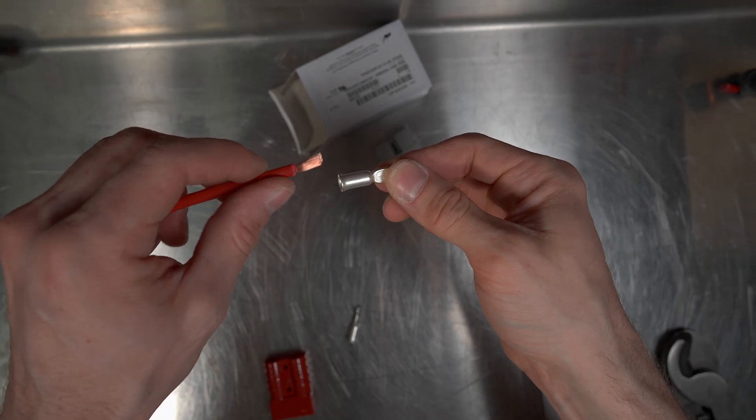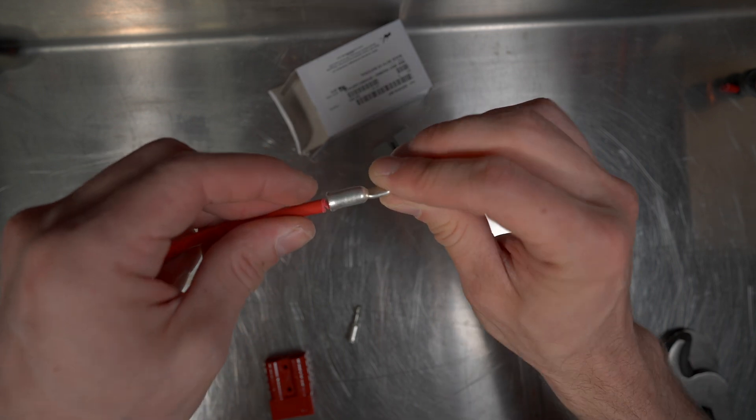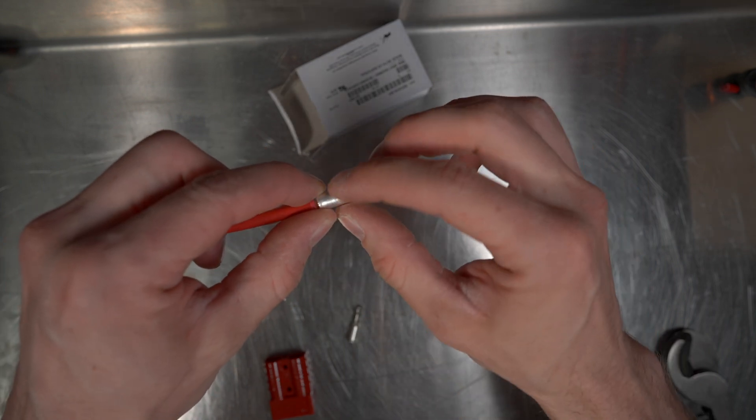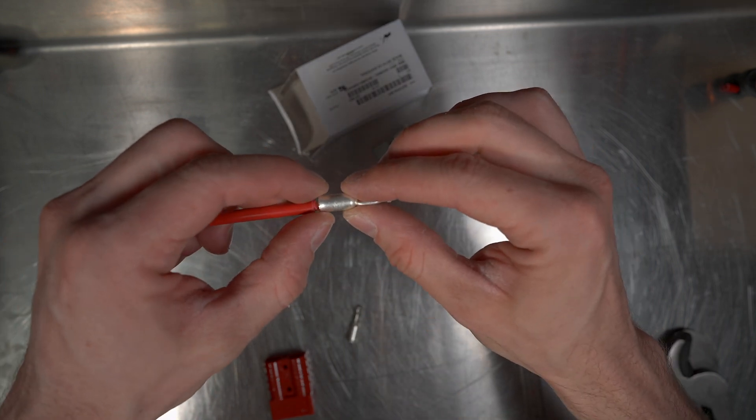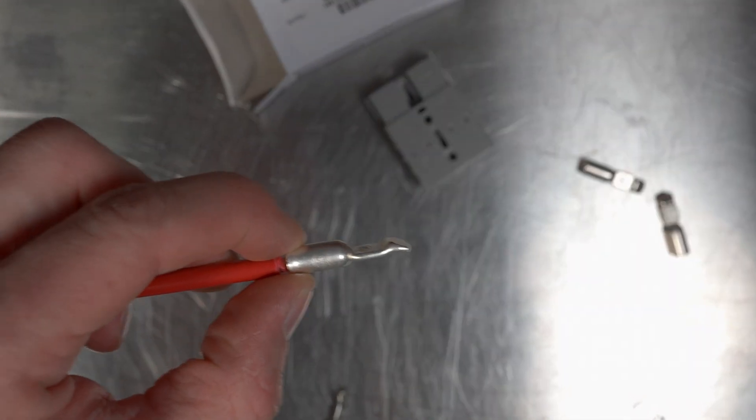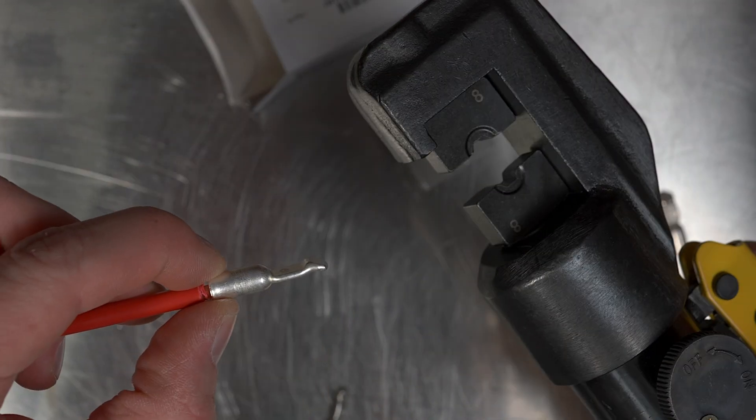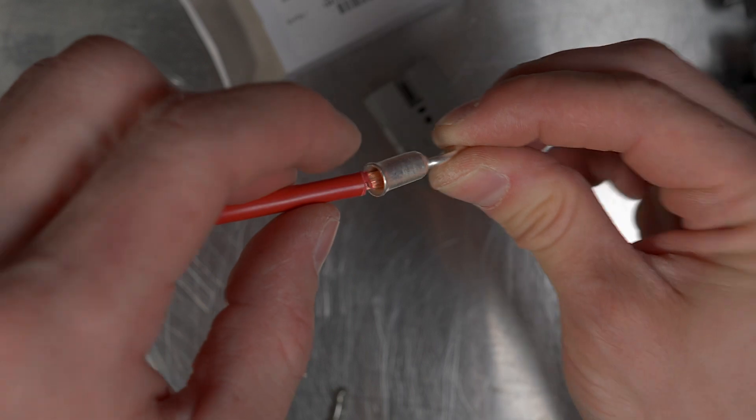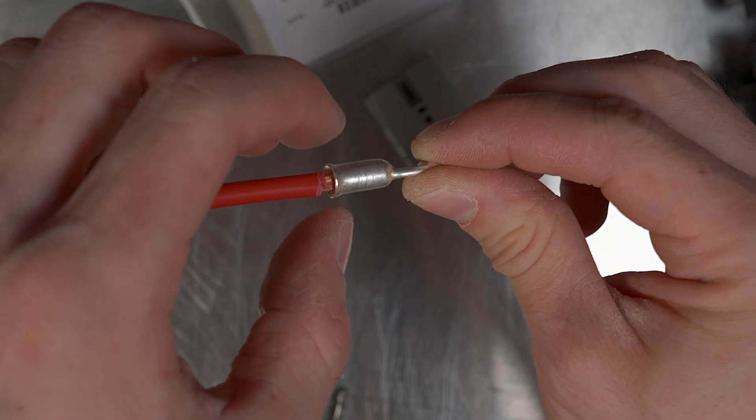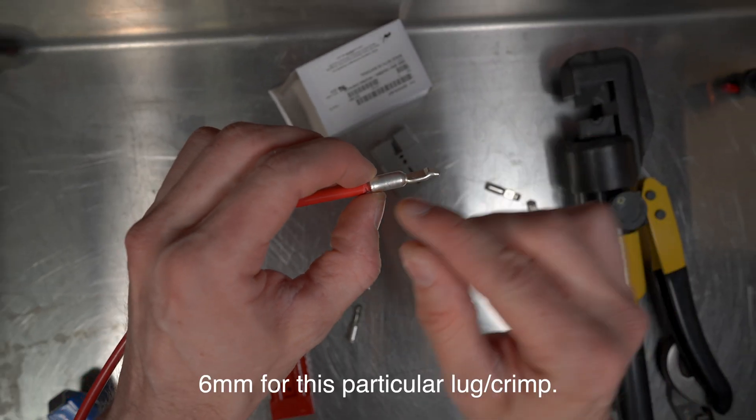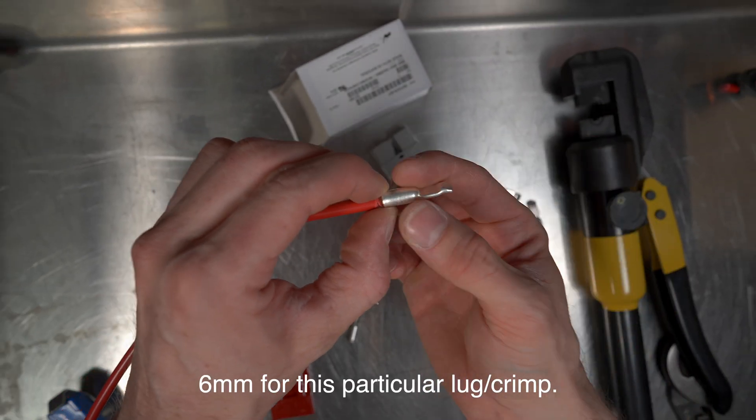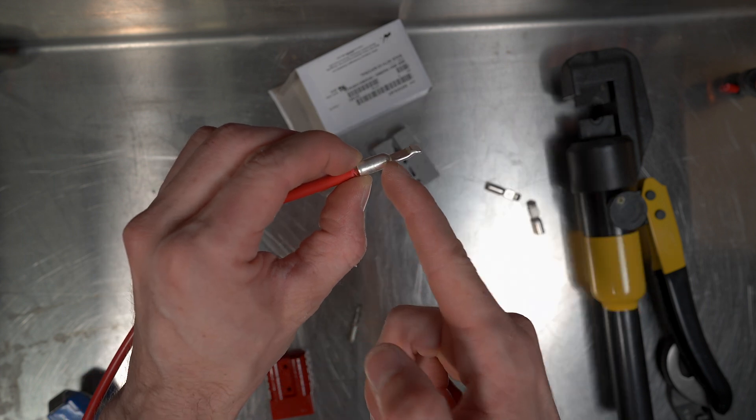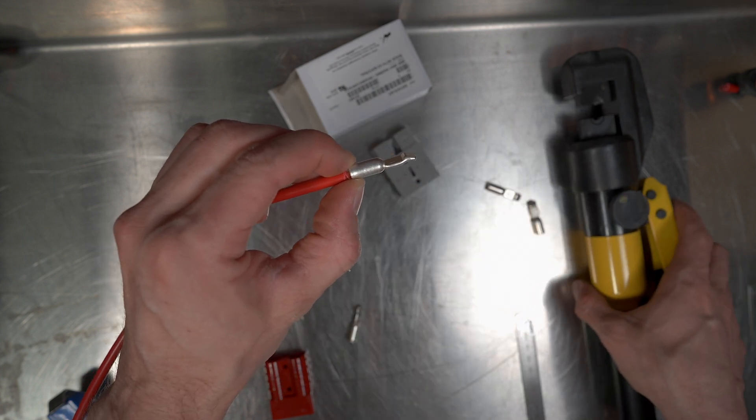So we roughly have our 14 millimeters there. 8 gauge, perfect fit. Now we make a crimp. 8 gauge being 8.3 mil, using an 8 mil die. Single crimp. And basically what we want to do is this bell shape at the end, we want to leave untouched. We want to go just inside that and make our crimp, leaving both ends of the lug untouched.